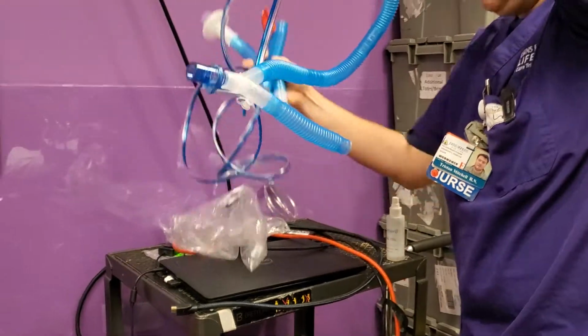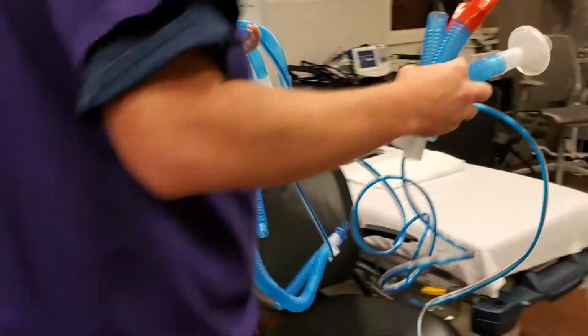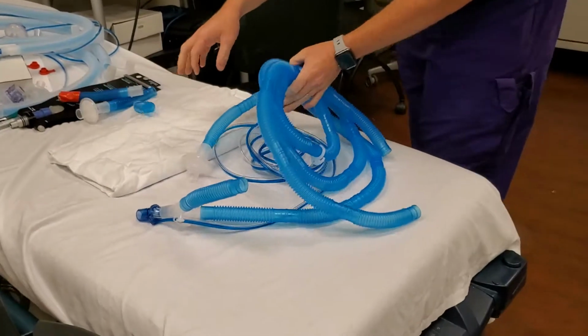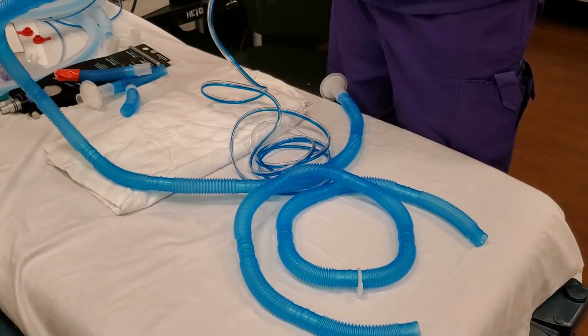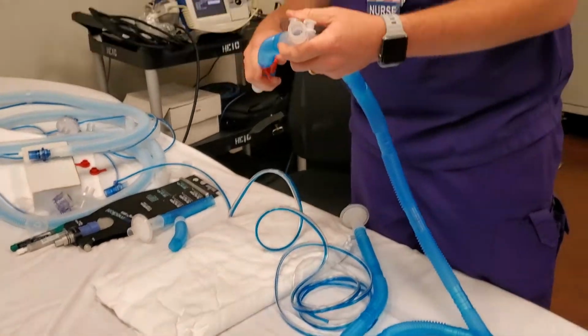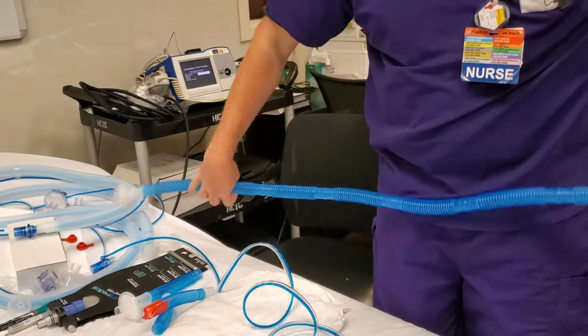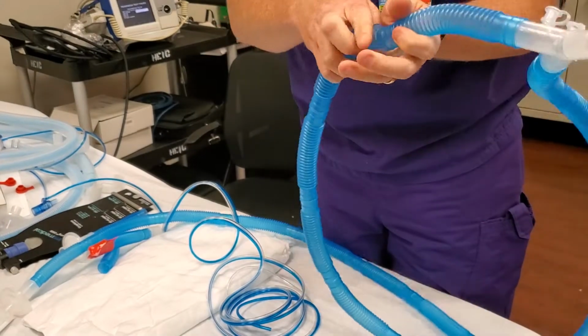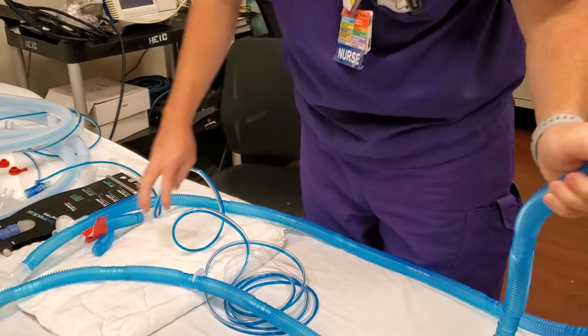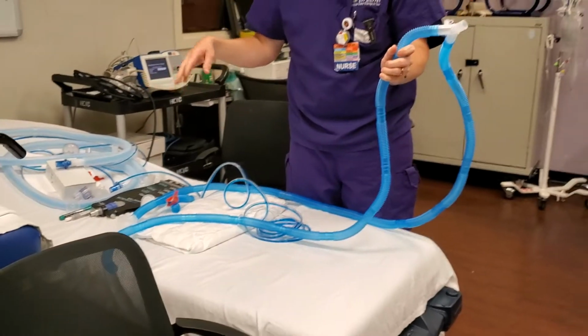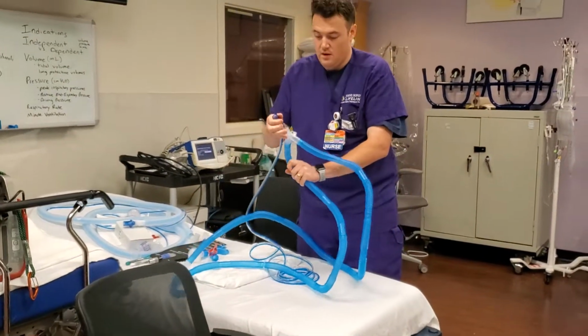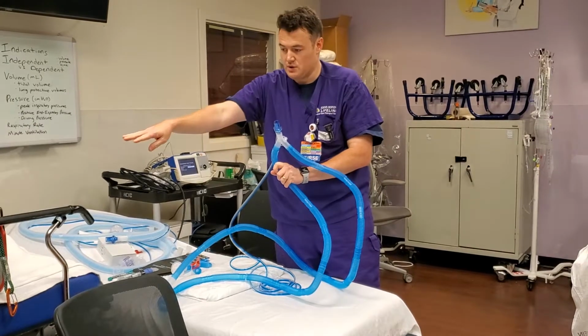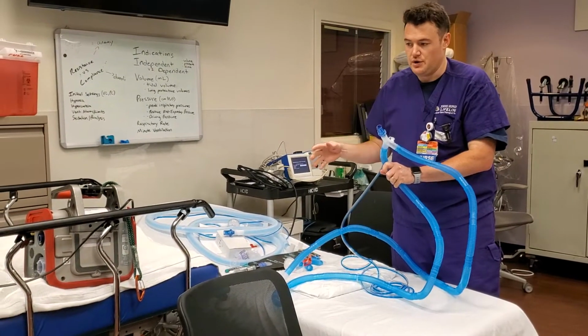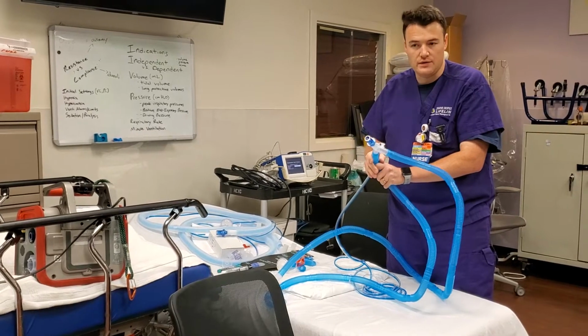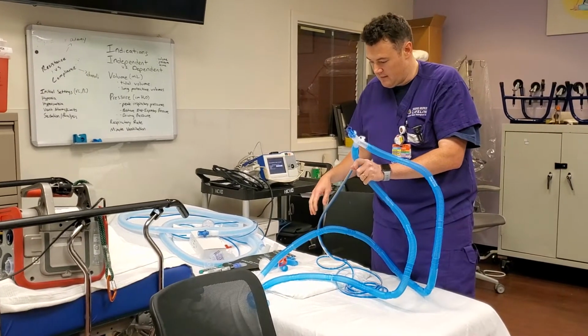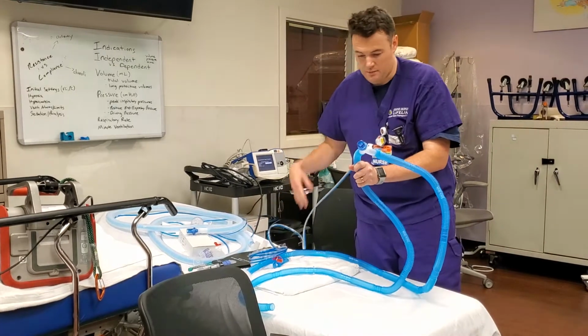Perfect. So we'll come just over here. And so obviously when we take it out of our bag, it's going to be just a single dual lumen tubing that's going to have your one lumen here and one here like such. So we're going to complete our regular pre-op check on the ventilator without incident. We're just going to put that there. We have our flow sensor tubing here, which is going to go on here, hook it up to our ventilator like we normally would with a dual lumen setup. Do your pre-op checks, make sure everything's good there before you cut the tubing and get it ready for putting our nitric in line. So once we've done our pre-op check, everything looks good.